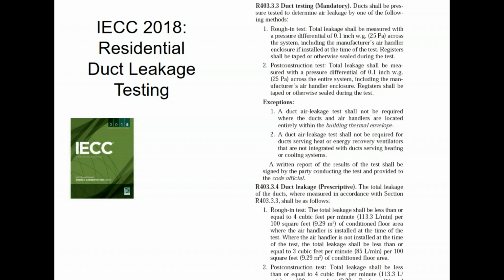I'm just giving you my interpretation of it. If the ductwork goes outside the thermal envelope, meaning it goes into an attic, crawl space, exterior wall, something like that, it still has to be sealed, inside or outside the envelope. It still has to be sealed, but then it also has to be duct leakage tested.